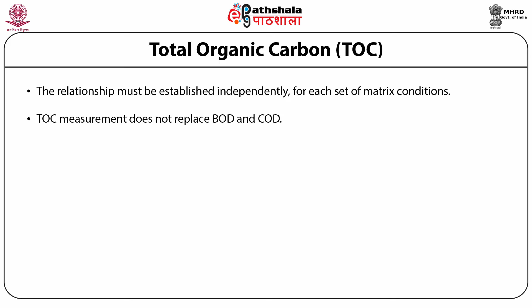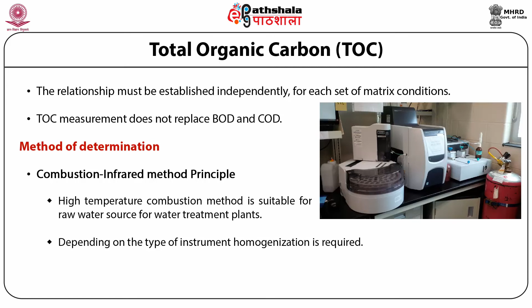For determining the TOC, that is total organic carbon, the combustion infrared method is preferred. In this method, high temperature combustion is suitable for raw water sources for water treatment plants with low turbidity and smaller particle size of suspended matter. Depending on the type of instrument, injection port and needle, homogenization is required to avoid clogging and achieve repeatability of the analysis. The instrumental TOC method utilizes a high temperature catalyst and oxygen, or lower temperature, less than 100 degrees centigrade, with irradiation, chemical oxidants or combinations of these oxidants to convert organic carbon to carbon dioxide. The carbon dioxide may be measured directly by a non-dispersive infrared analyzer, or CO2 may be titrated chemically.